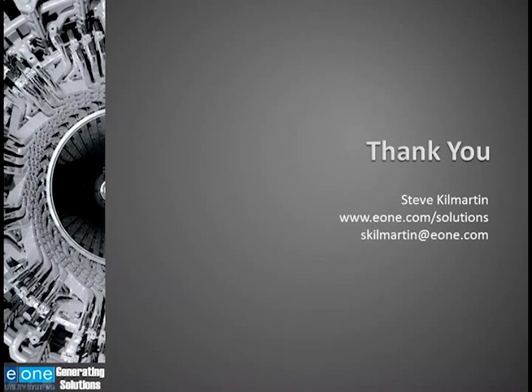Okay, and it looks like we have one final question here. Typically, what is the cost of hydrogen-cooled generator failure, and how is that different from an air-cooled failure? A generator can fail for many reasons. For instance, and I am not a generator expert, but I've sat in a lot of conferences and a lot of papers, so I hear about these problems. If, for instance, you have a bushing problem, it would be a lot less money to repair that bushing than if you had a stator core that had to be restacked or partially stacked.